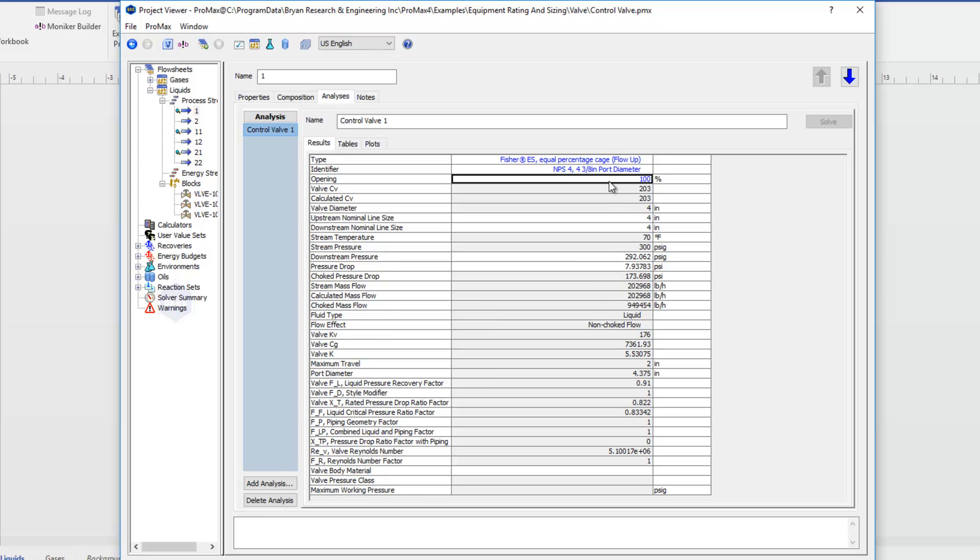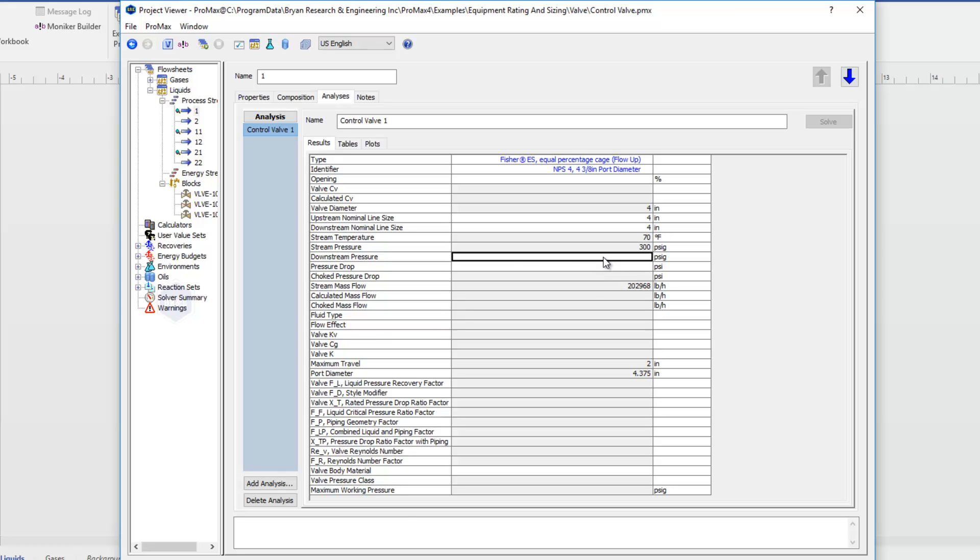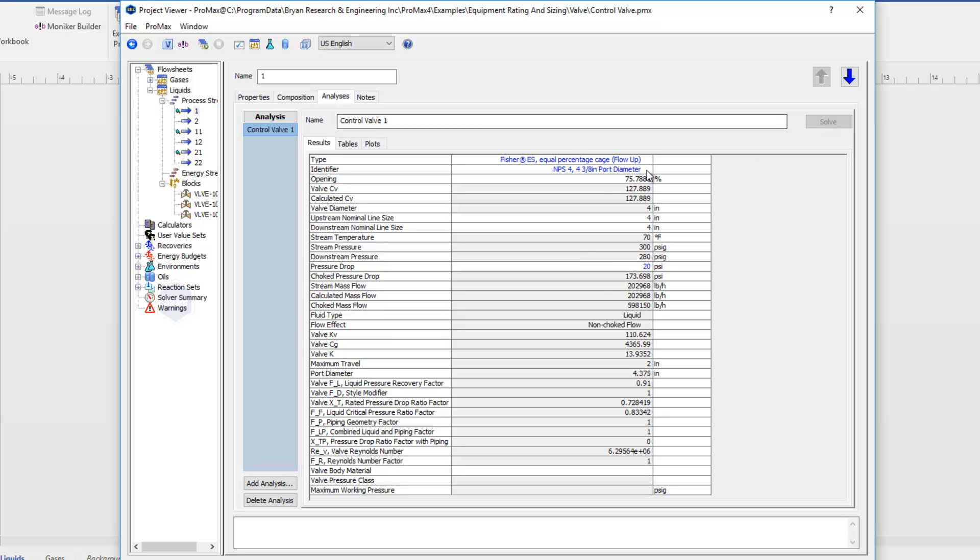If I don't want to define my opening, instead I want to know what my opening should be, I could instead type in either a pressure drop or my downstream pressure. Either one would work. Let's say we want a 20 pound drop. If I click Solve, Promax calculates my opening and my valve CV for me.